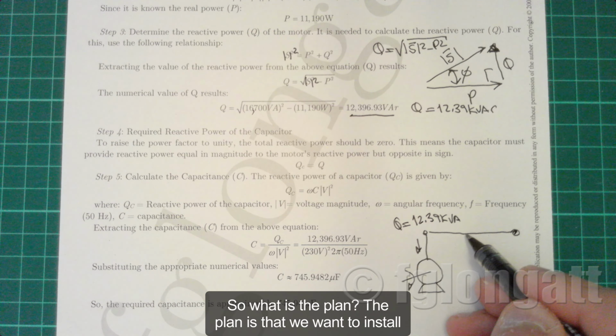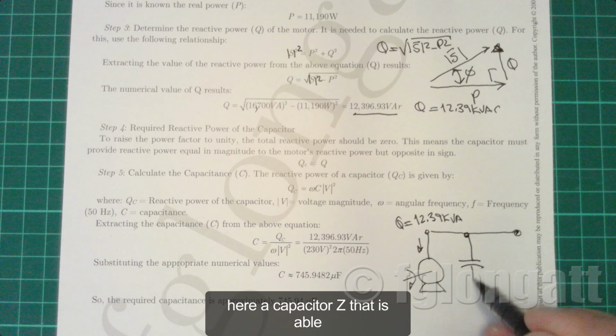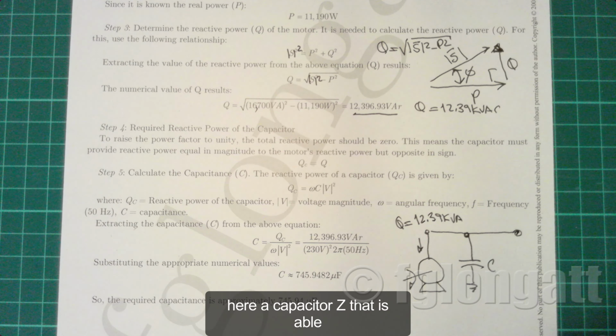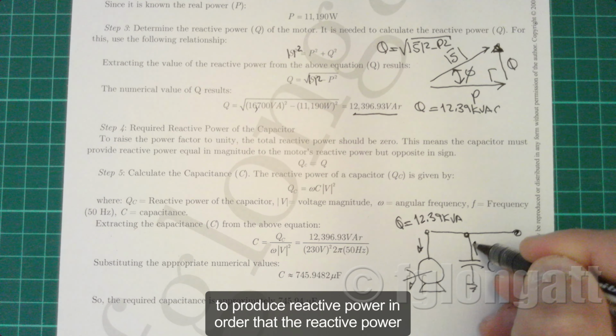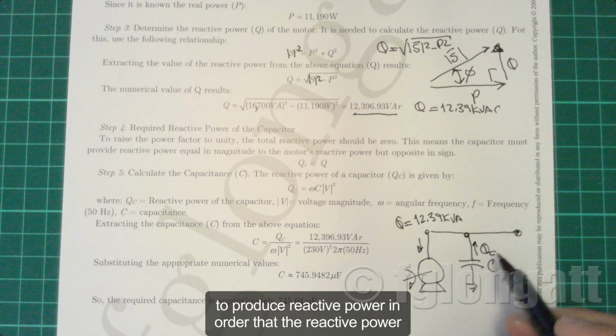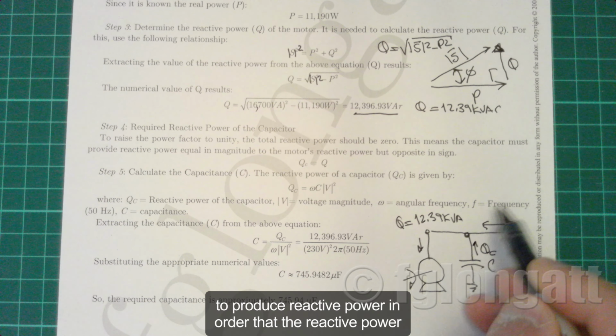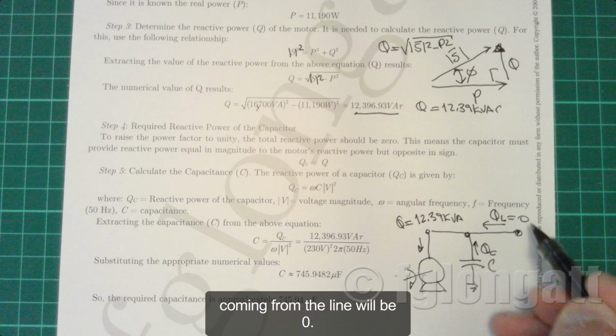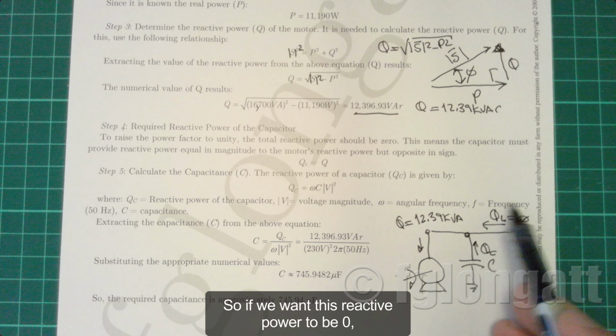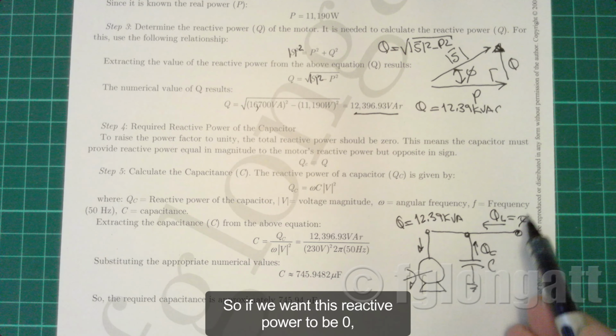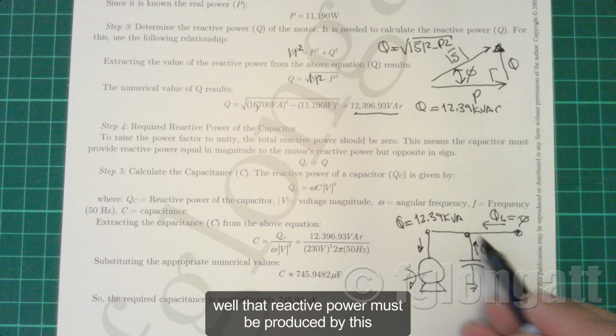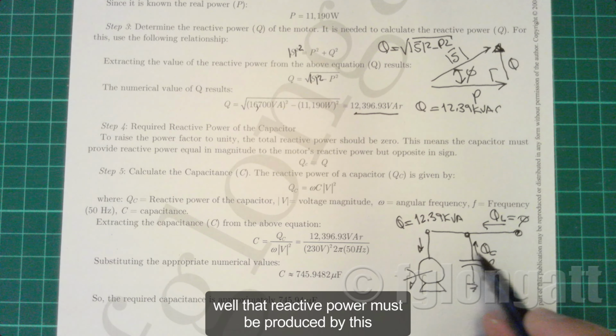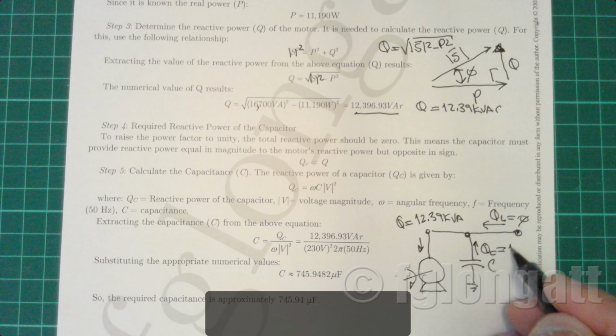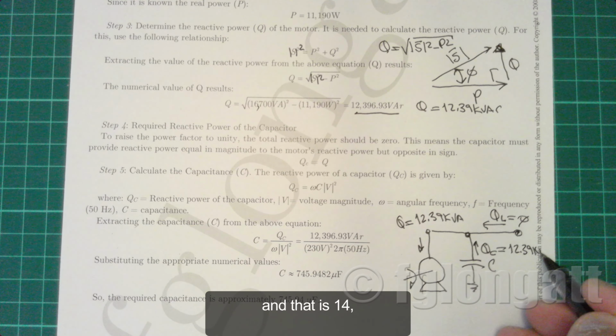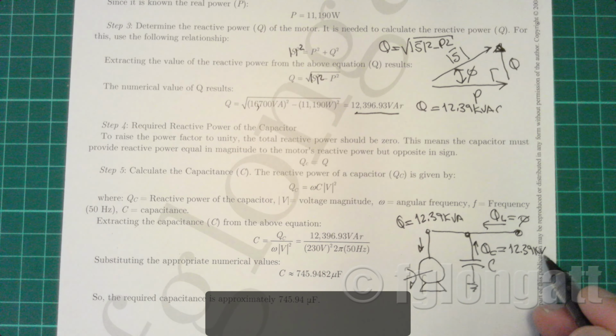So what is the plan? The plan is that we want to install here a capacitor C that is able to produce reactive power in order that the reactive power coming from the line will be 0. So if we want this reactive power to be 0, that reactive power must be produced by this capacitor, and that is 12.39 kVAr.